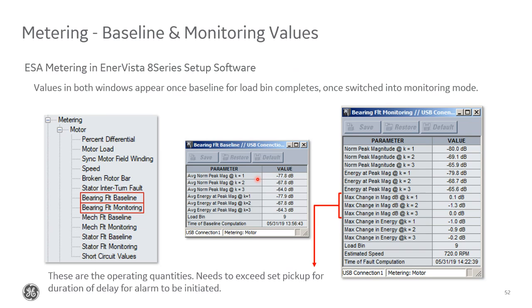Ideally, you'd want the baseline readings to be consistent. And in that case, a small deviation value would be seen. If you have a really high standard deviation value, that might mean the accuracy of the ESA element inherently might not be as great. And just to note, all the values you see here, you can also see directly on the relay front display.